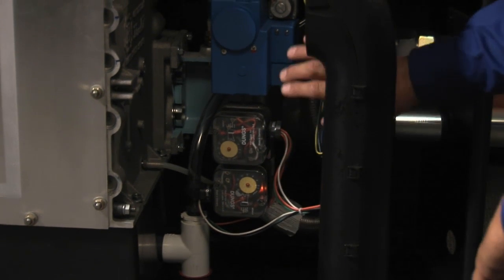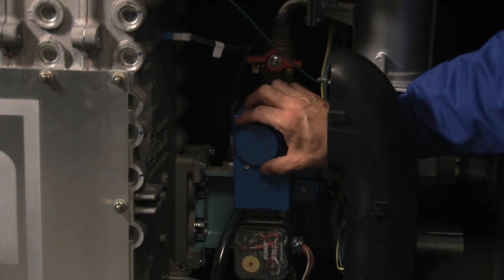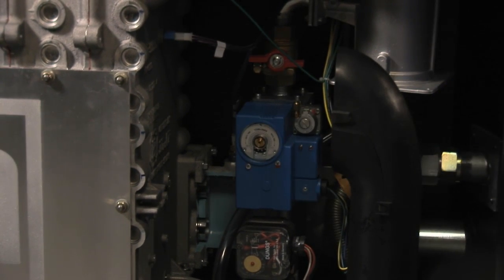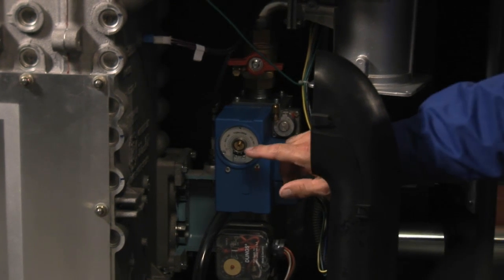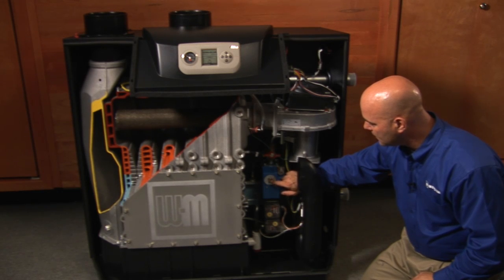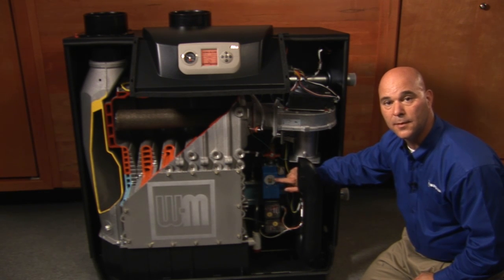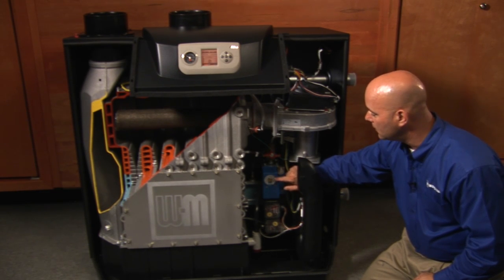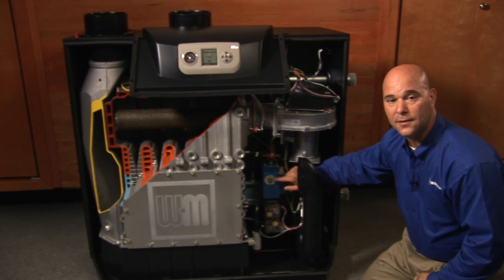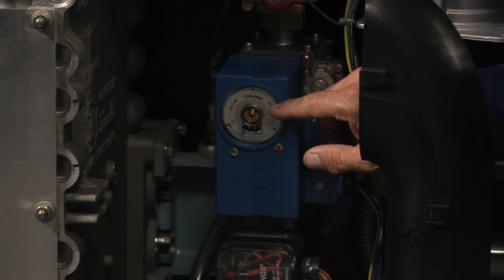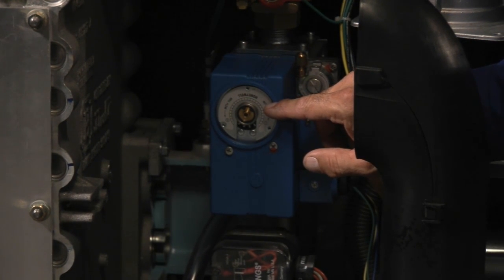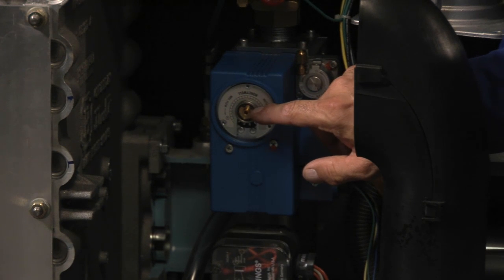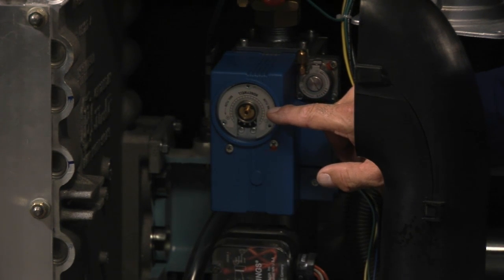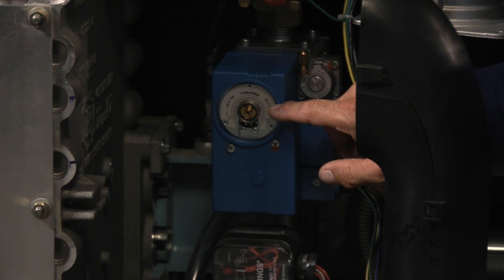On the gas valve itself, if you need to make adjustments during startup, this cover removes, and you'll put the Allen key right into the center here, and it has a plus and a minus sign for minimum flow and maximum flow. And you will adjust this about 1/8 of a turn, 1/16 of a turn at a time. This is very sensitive, so as you start to make your adjustments and you're fine-tuning the boiler, you'll make very slight adjustments at a time.